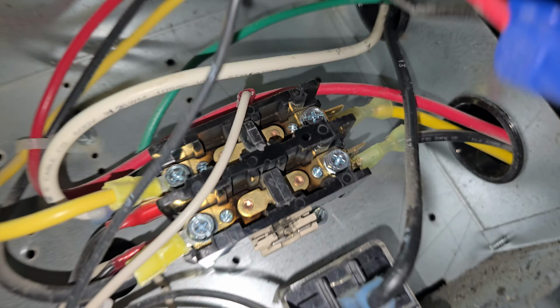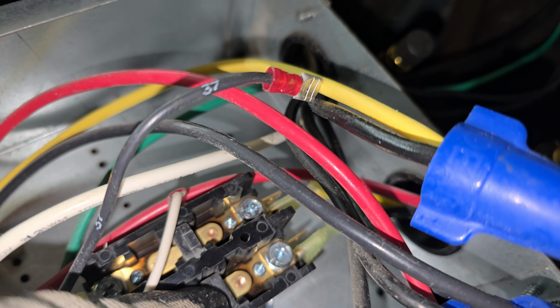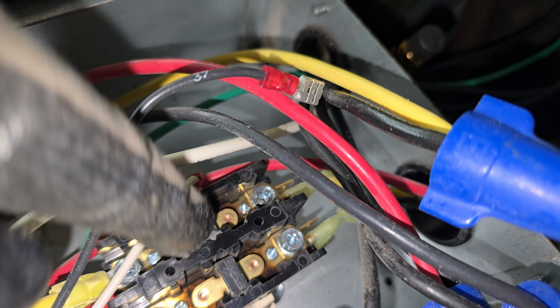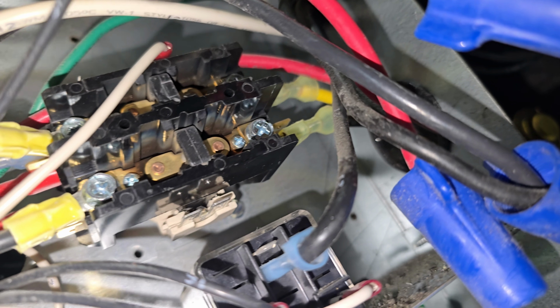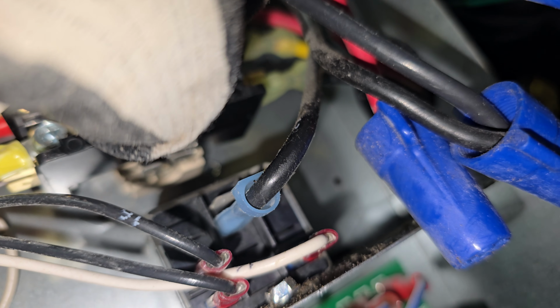So you're looking at the contactor here. The contactor is really in bad shape. It's kind of stuck in. One of these leads is sticking and the other one is not sticking. Even though I took out my low voltage contact, it's still not responding.